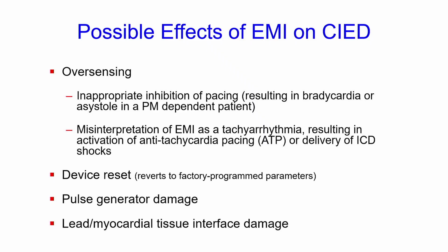If it's a defibrillator, it can interpret the EMI as cardiac electrical activity, which can result in activation of anti-tachycardia pacing or even inappropriate shocks. So oversensing is one of the primary problems that can occur with EMI. You can also have device reset, which reverts to the factory program parameters. You can have pulse generator damage, and there can be damage at the lead myocardial tissue interface.